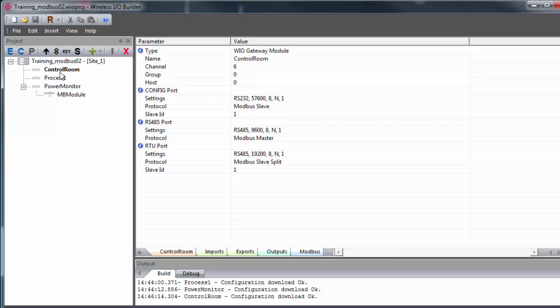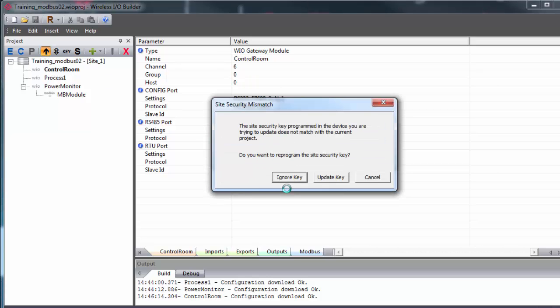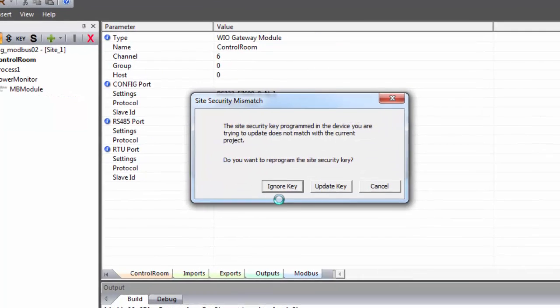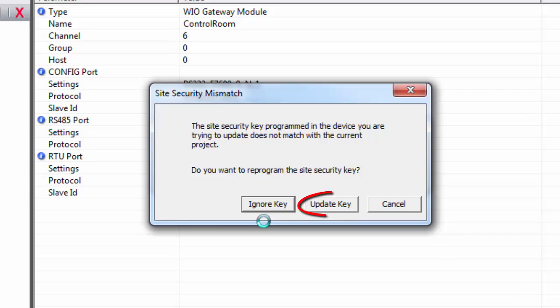If, however, the gateway has been configured previously, you'll get a screen like this asking if you want to update the key or ignore it. If you're setting up a new network and are already planning on updating all the gateways, you can go ahead and choose Update since you want to use the new security key anyways. If, however, you have an existing network that's already up and running and you just want to make changes on the configuration of one or two gateways...